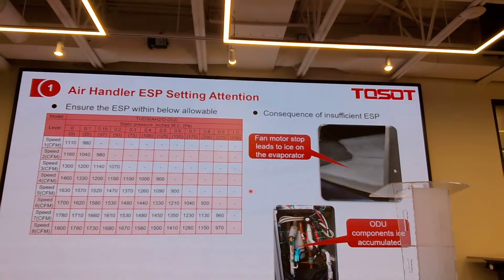And the pressure, what I mean here is the compressor should turn on at least 15 minutes, which means you make it run until stable. Then you can check the pressure. That is okay. If at the very beginning, let's say 5 minutes, you check the pressure, it's not that good.